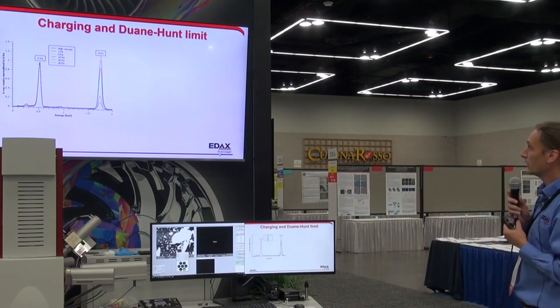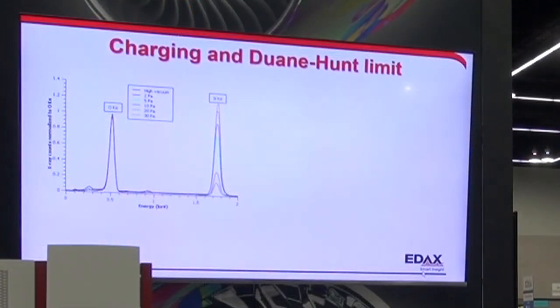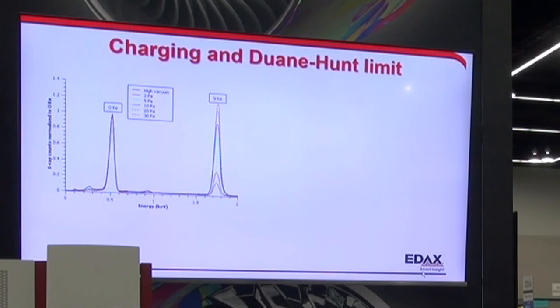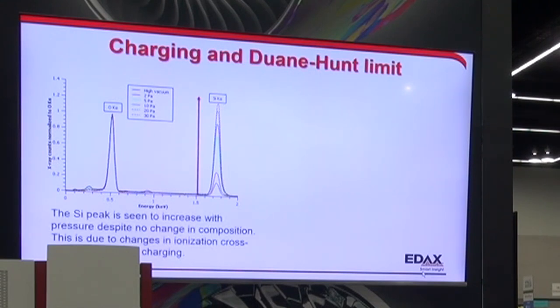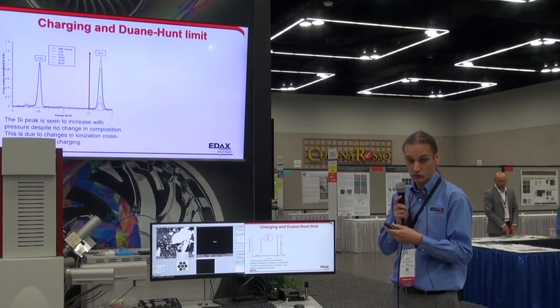This is a spectrum from a silicon dioxide sample. I'm running it in high vacuum and then at increasing pressures throughout. I've normalized everything to the oxygen peak. If you look at the silicon peak, you can see that as I increase my pressure, I get more and more silicon signal — even though this is the same sample with no change in composition. I get a change in the intensity of the x-rays.